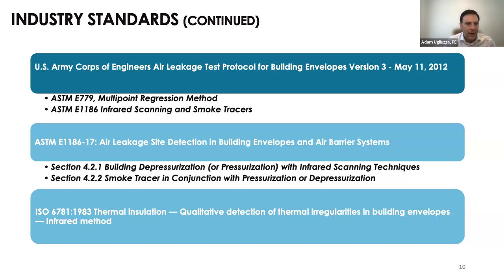So ASTM E1186 is a great diagnostic air leakage site detection standard. There's a number of procedures in there. The two that are most commonly used when you're doing whole building air tightness testing are infrared scanning with pressurization and the same thing with smoke tracers. Basically, you create a pressure difference, and that enhances the image when you're doing an infrared scan, or with the smoke tracer, it creates air currents that the smoke can pick up and you can figure out where it's coming from, where it's going. So those two tools in conjunction are very powerful in helping you determine where that air leakage site is in the building.